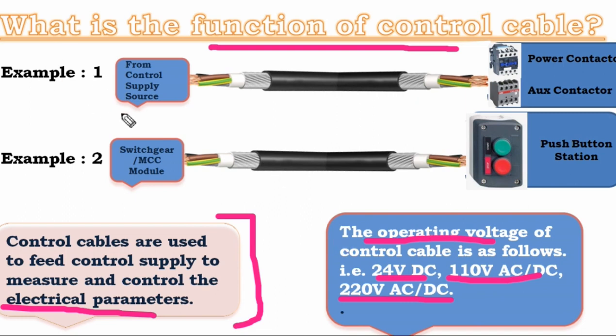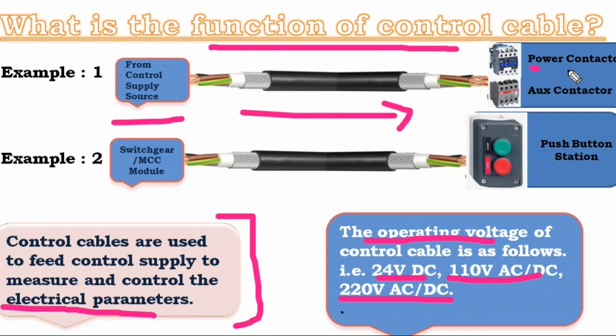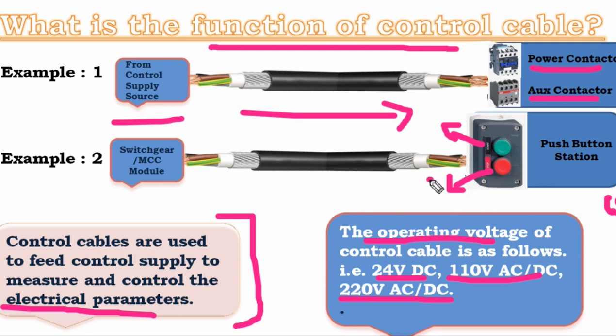In example one, the control supply is available at the source — it may be 24V DC, 110V DC, or 220V DC — and it is transmitted through the control cable to act on the power contactor or auxiliary contactor. In example two, the control supply is available at the push button station. The green push button indicates starting the motor or switchgear elements, and the red push button indicates stopping the motor. The control supply is transmitted from the push button station to the switchgear or motor control module.